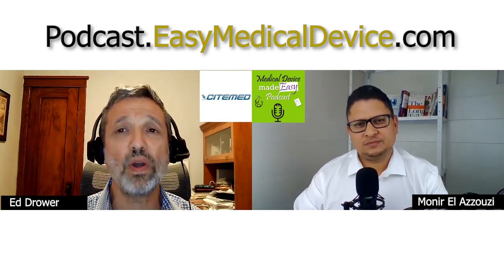There's quite a few steps involved, but I'll try and break it down simply for the audience here. The first thing that you really have to understand is a literature search is a systematic approach to trying to find enough information about your product or device so that you can make an assessment of benefit and risk on your device. And this will help flow into the ultimate reports that you're going to need, which will be the CER, and then later on you'll have to define your post-market clinical follow-up and other types of reports.